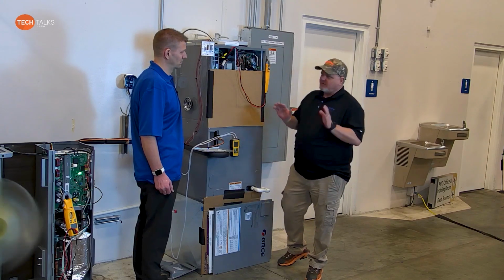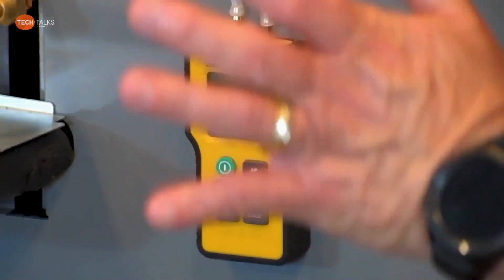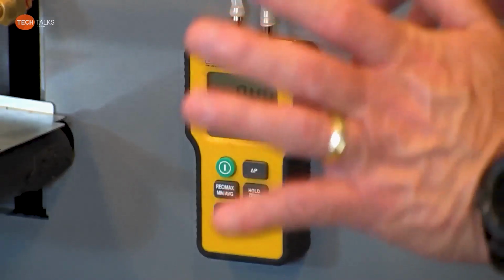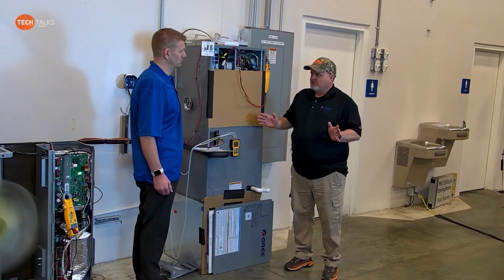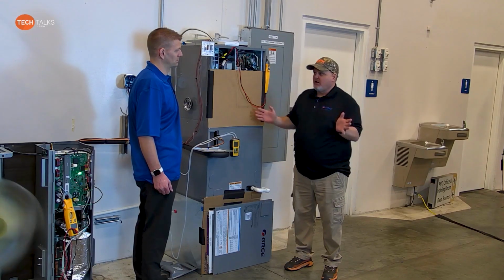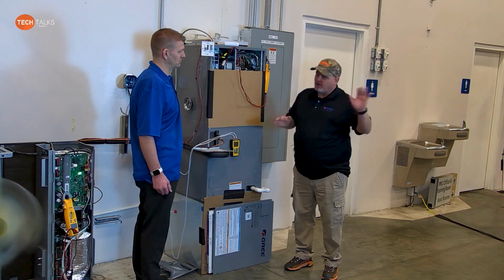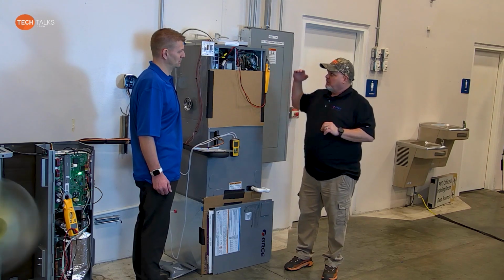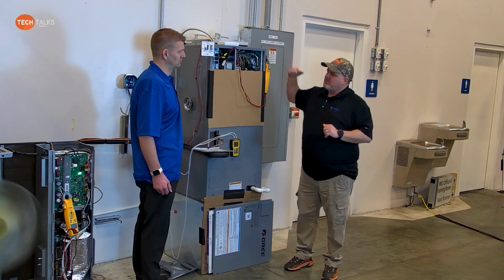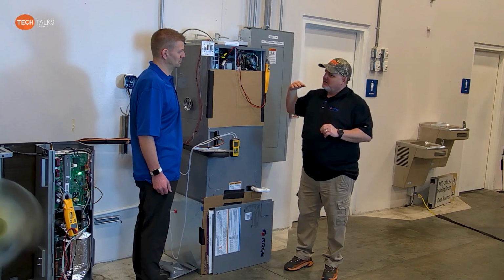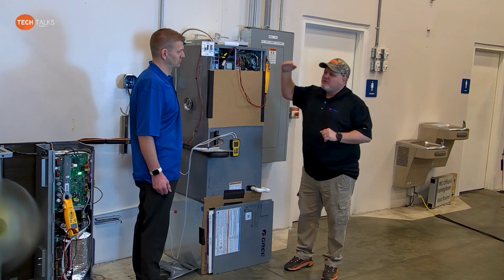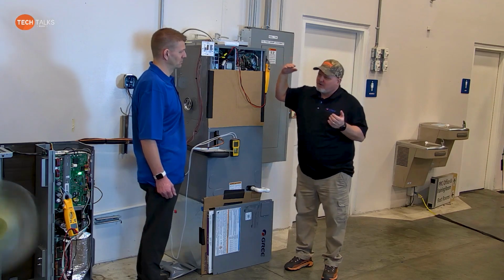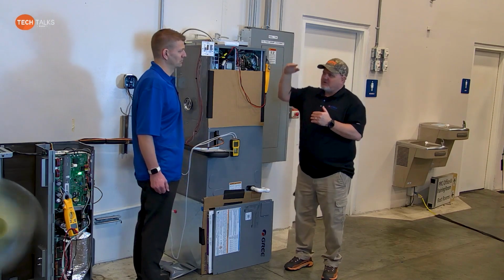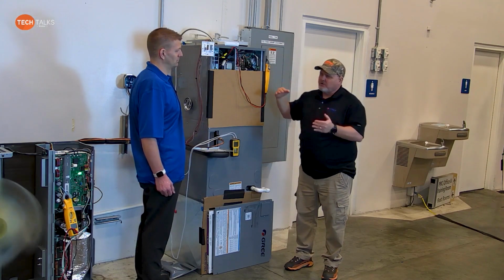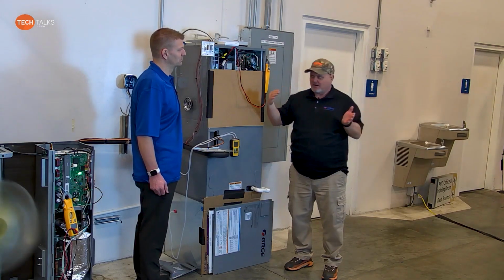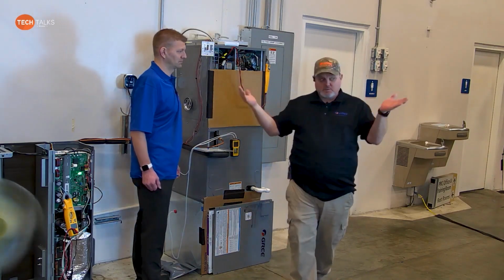I got 0.5 static. For residential, that's not bad, okay? But let's say that was 0.8. That's horrible, and I'm not moving enough air. More than likely, we'll look at it on the blower chart. But if I increase the blower speed, I'm already not moving enough. I can't move 3 tons of air in the existing ductwork. If I increase the blower speed, I don't know that that's going to help me, is what I'm getting at here. So let's prove the theory or disprove the theory.